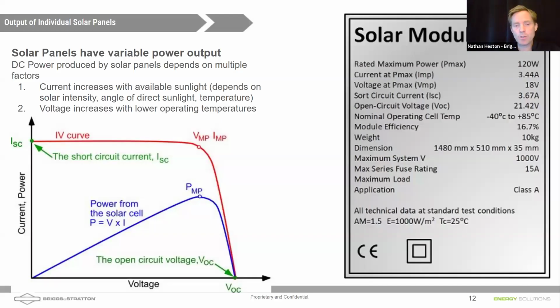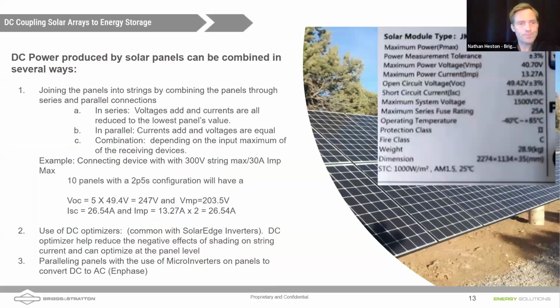Keep in mind that in high temperatures, you'll see more of a voltage drop on the panels. So the voltage output of a panel will change with temperature. In cold temperature conditions, what do we see on the voltage, Daniel? A higher voltage. Yes, and the current is almost proportional to the amount of light that the panel is receiving. So that current is almost a direct reflection of how much light that solar panel is absorbing. It goes up and down with the angle of the sun and with the intensity of the sun. So if there's some cloud cover, etc., you'll see the current modulating a lot. The voltage mostly changes with temperature.